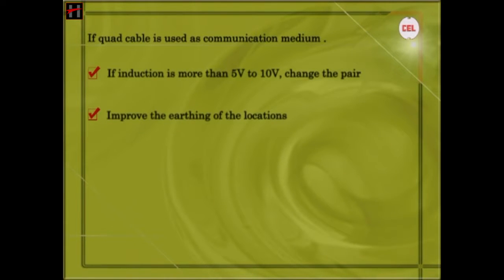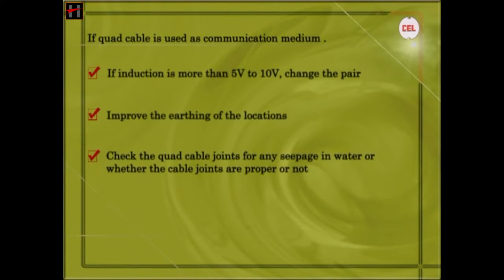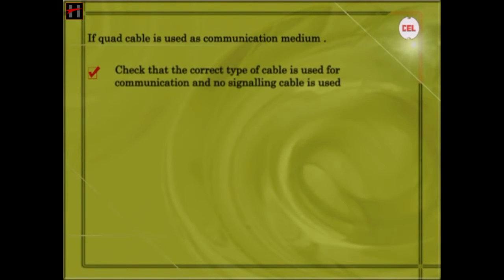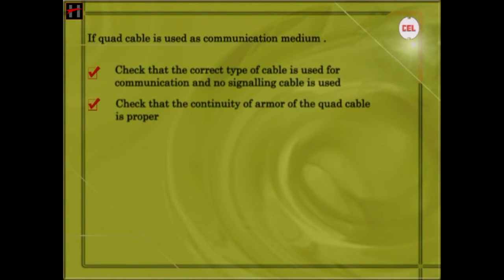Improve the earthing of the locations. Check the quad cable joints for any seepage of water or check whether the cable joints are proper or not. The armour of the quad cable can be earthed separately. In case the problem is not rectified, check that the correct type of cable is used for communication and no signalling cable is used. Check that the continuity of the armour of the quad cable is proper, and check and verify the following parameters.